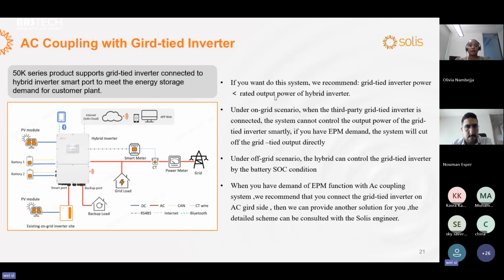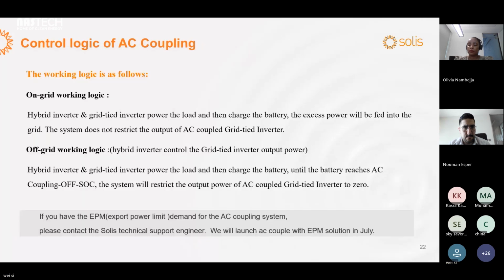But here you should notice that the grid tie inverter power should be less than the hybrid rated power, and if you have the EPM demand, we call it export power management or the limit. When on grid, all the inverters follow the grid frequency and voltage. But when it is off grid, we have the over frequency derating function on the smart port and the AC port, so the system can be safe when you are using it. Okay, it is the working logic.